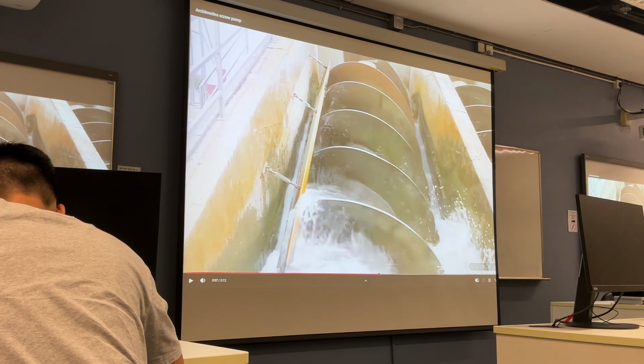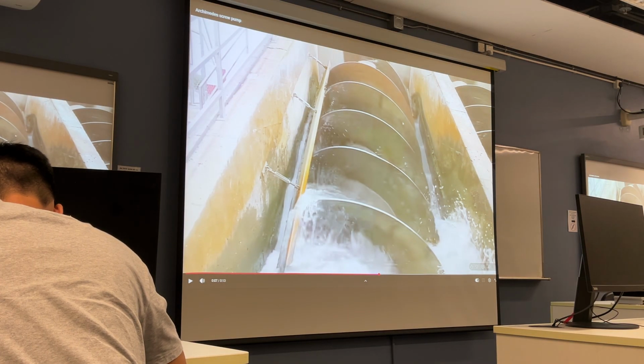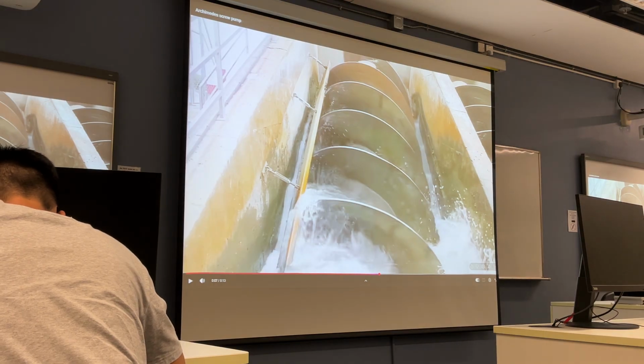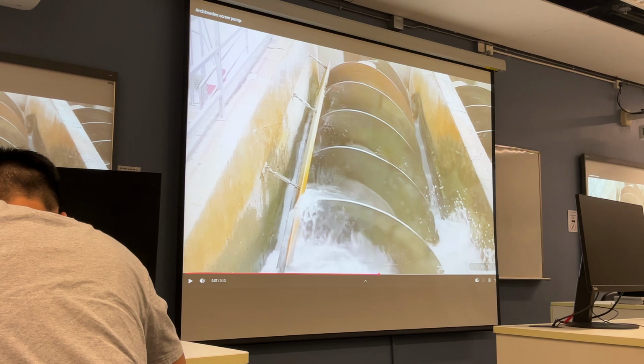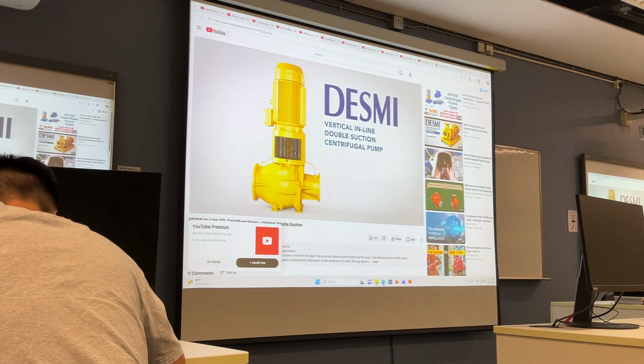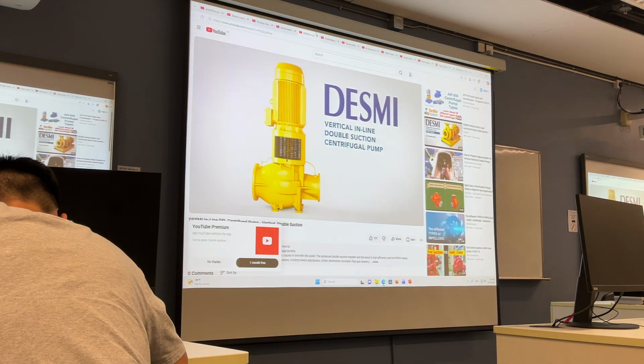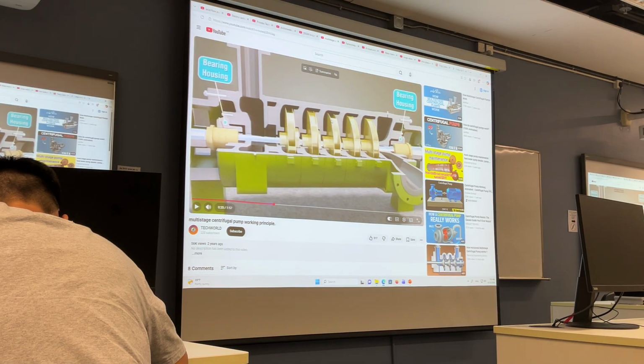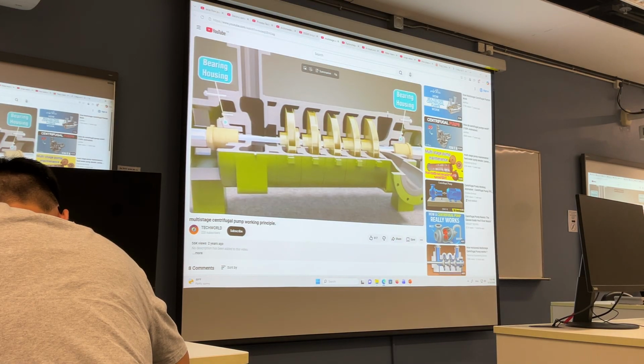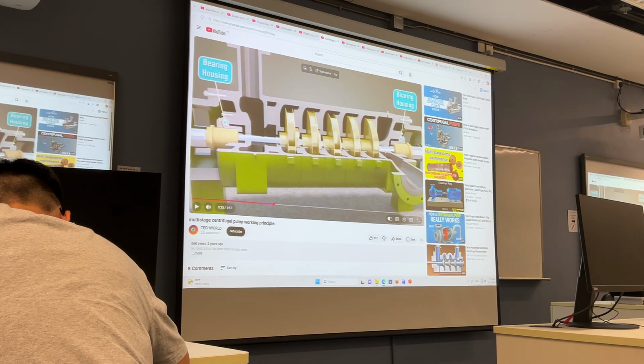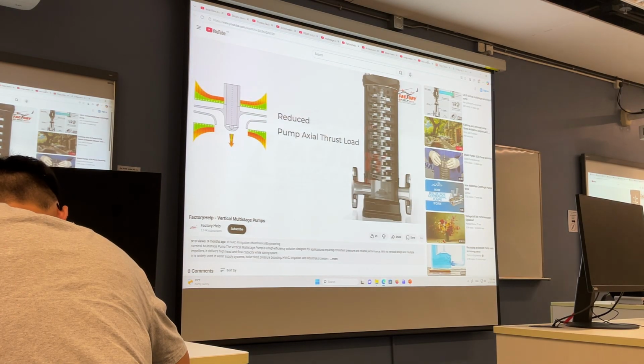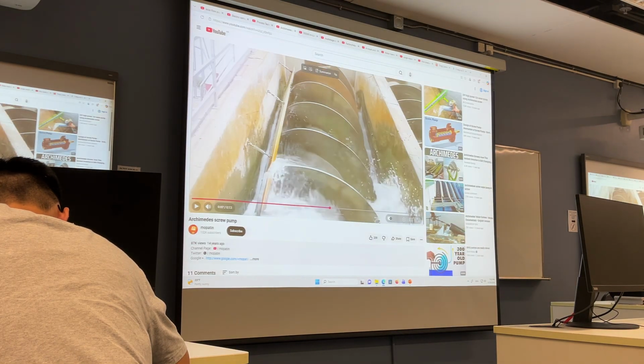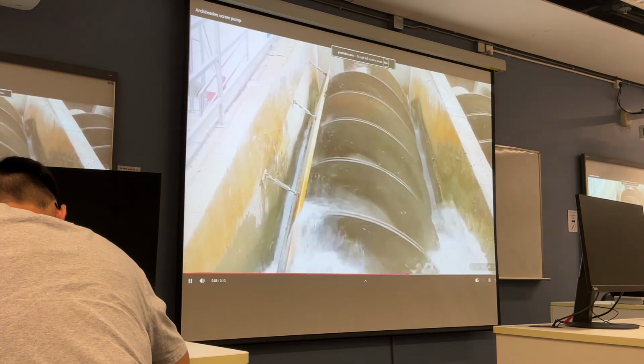So you see that the water gradually moves up to the higher location according to this effect. For the common centrifugal pump, you see that the gap between the shell, the casing, and the impeller is very narrow. If there is big stuff, the clogging, it is very easy to damage the centrifugal pump. So in some scenarios, this kind of screw pump is used to transfer the water.